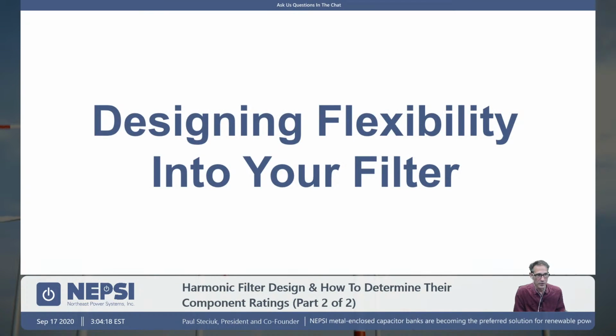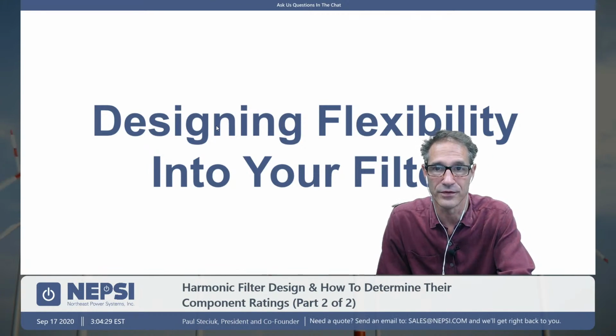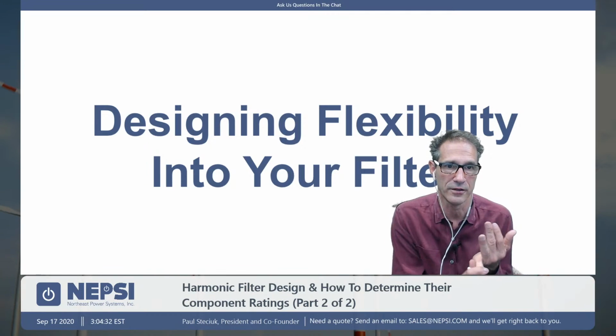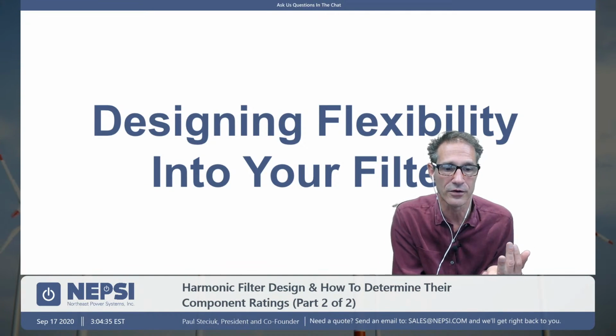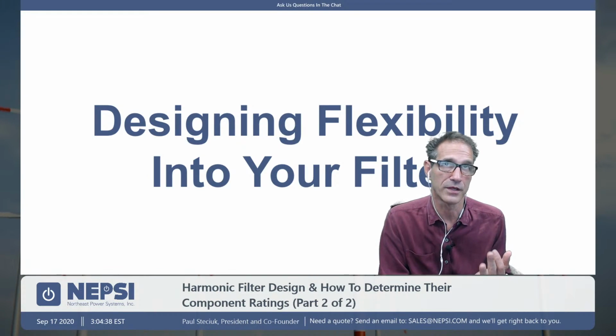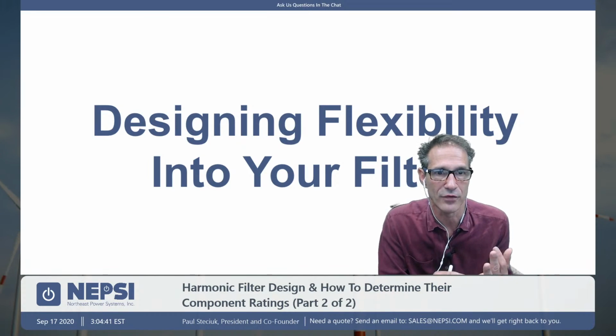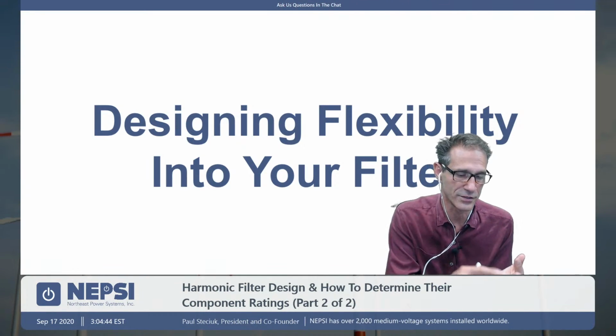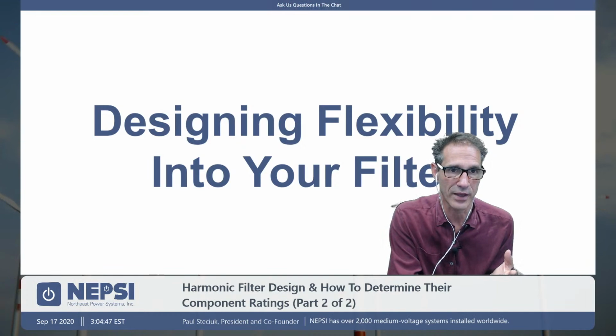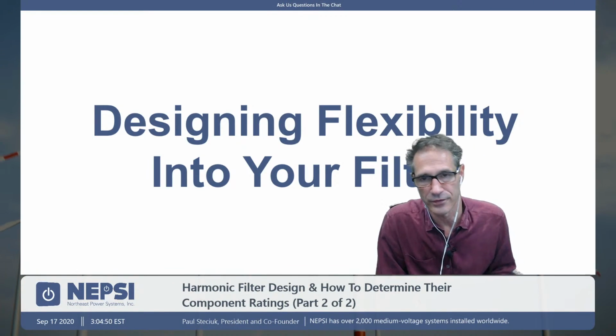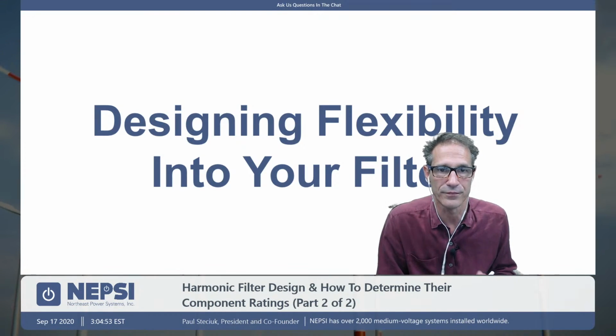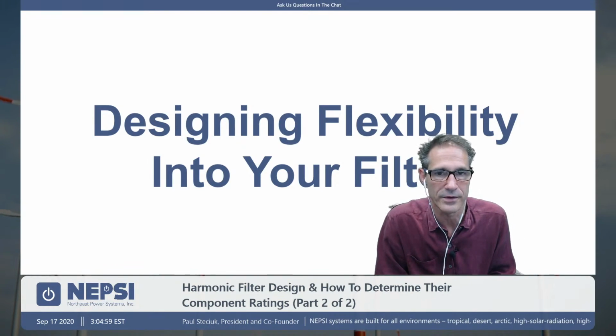So we have other things in the future that we will be talking about. One of those would be designing flexibility into your harmonic filters. We often recommend that you design flexibility into your harmonic filter. That might be the ability to change the kVAR rating of the stage, the tuning point of the stage, being able to tap the reactors to move things around. So we have another presentation in the future about putting flexibility into the filter to allow for the unknown, really is what it's about.